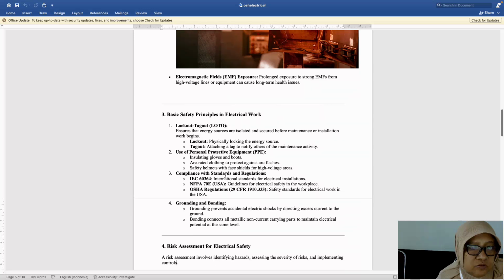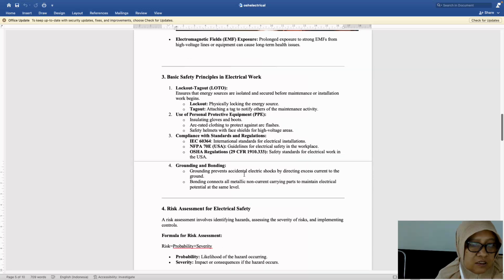And then compliance with standards and regulations. This is the IEC 60364, the international standard for electrical installations, and then NFPA 70E, USA guidelines for electrical safety in the workplace, and then OSHA regulation 29 CFR 1910.333, safety standards for electrical work in the USA. And then grounding: grounding prevents accidental electric shock by directing excess current to the ground. And then bonding: connecting metallic non-current-carrying parts to maintain electrical potential at the same level.